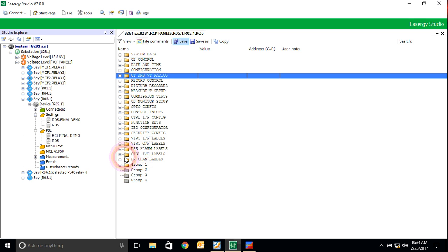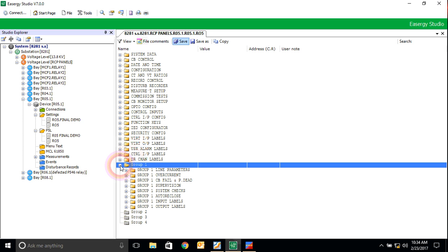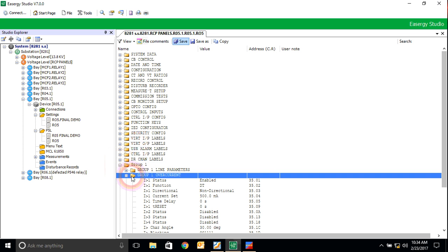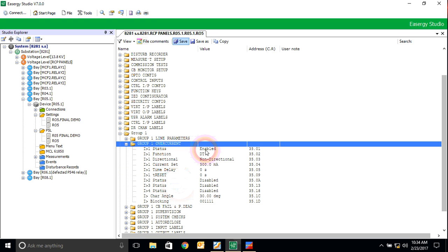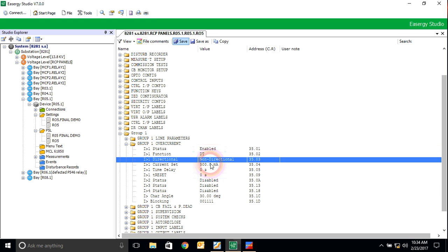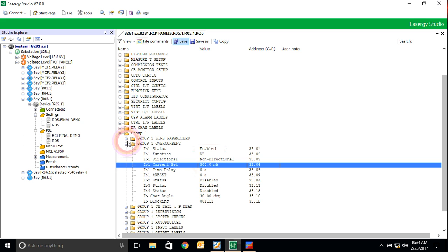After this parameter you will go to our function. First I will test independent of synchro, then after I will merge the synchro function inside. This overcurrent is what I will initiate; I will enable definite time non-directional with 0.5 as the setting, no more.